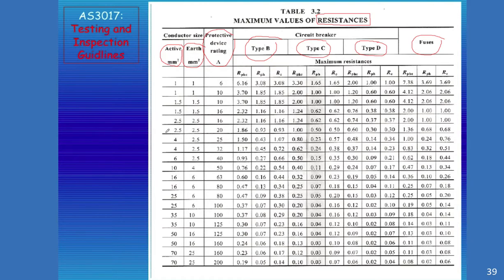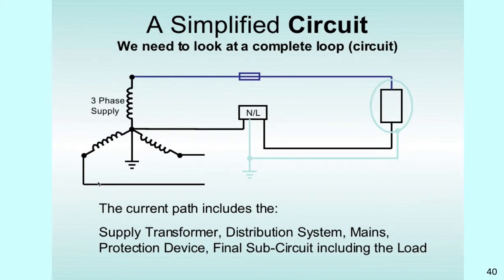The one that we just looked at was a current rating of 20 amps. So, assuming that was being used on a final sub-circuit, and we had two and a half square mil for the active, and the Earth was also two and a half square mil at 20 amps. And we're using a C-type circuit breaker. We would be looking in here. And if we're looking at the whole loop, the protective, the phase and the protective Earth combined, the whole loop combined is this one. So, everything would have to be less than one ohm.